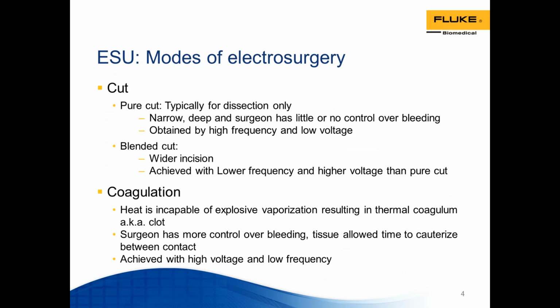When we're in these modes, we can either cut or we can coagulate. So in the cut operation, there's a couple of different ways that we can do this. Pure cut is typically for dissection only. It's narrow and deep, and the surgeon has little or no control over bleeding, and it's obtained by high frequency and low voltage. The blended cut makes a wider incision, and it arrives with lower frequency and higher voltage than pure cut does.